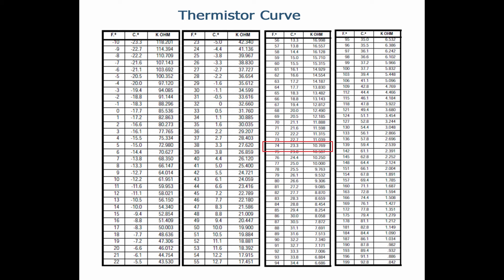The way you would do that is you would take your ohm reading and go to the chart and look for the corresponding temperature. Most likely if your machine's in auto, your product should be between 17 and 22 degrees Fahrenheit, so that would correspond to somewhere between 43 and 50K ohms. If the reading you get is off by more than five degrees or if you get an OL reading or an open reading, it's probably time to replace the thermistor probe.